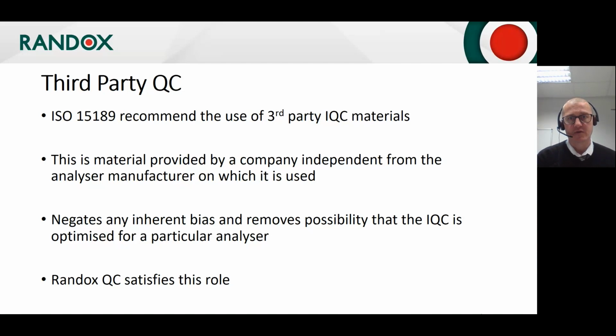ISO also recommends the use of third-party IQC materials. This is material that is provided by a company that is independent from the manufacturer of the analyzers on which it is to be used. This negates any inherent biases from the company providing the analyzer. Simply put, it removes the possibility that the IQC being carried out is optimized for a particular analyzer. The third party, in essence, has no vested interest in whether the QC performs better on one analyzer or another. Randox satisfies this role well as a true third-party provider of both IQC material and the EQA material that our laboratories use.